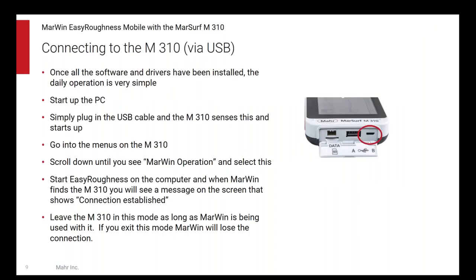So how does this work? How do you connect to the M310? You can do it, as I mentioned, two ways, via USB cable or Bluetooth. USB cable's pretty straightforward. Once you install the software and the drivers, the day-to-day operation is really simple. You turn on your PC. When it's booted up, you simply plug in the USB cable to the M310. It senses that the cable's been plugged in, it turns on. You go into the menu on the M310 and select MarWin operation. So it knows it's to be controlled by MarWin software and not by a touchscreen anymore. And you leave it in that mode. Then you start the Easy Roughness software on the computer and it will start up, search for connected units. You can have multiple units connected and it will find them and show connection established on each unit.